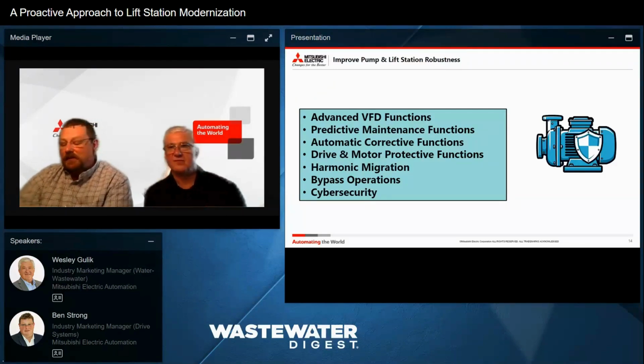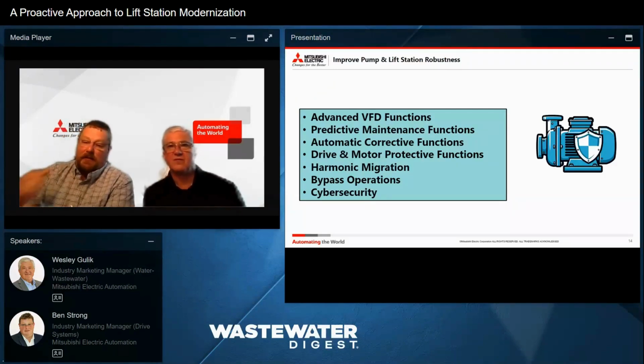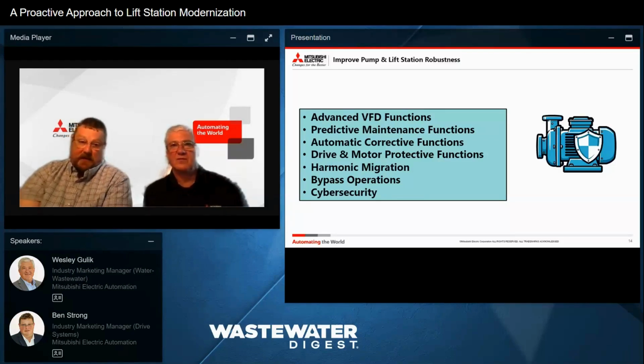So when we start talking about robustness, there's a couple ways to look at it. We can look at it from a mechanical standpoint, where if we operate as close as we can to the best efficiency point, we also operate with the least amount of risk mechanically with regards to having a system that cavitates or uses too much power for the flow rate. There's other things that can make your lift stations more robust. Almost every VFD manufacturer in this space that builds a pump drive has advanced VFD functions that when we ask operators, are you using this function? Are you aware of this function? Probably 60% of the time we're told no, which really surprises us because it's built in. You have it, whether you use it or not, but sometimes people don't use it. The predictive maintenance functions can be really powerful as well.